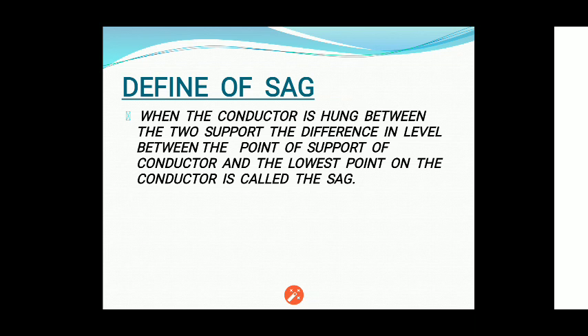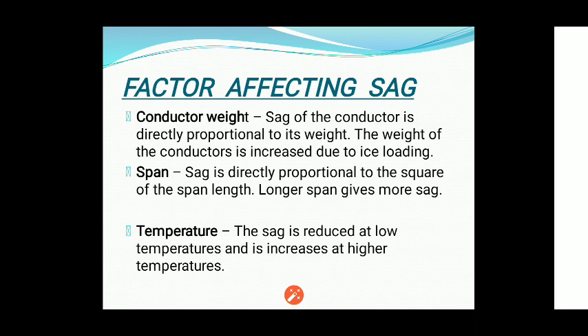Next we will discuss the factors that affect sag. The first factor is conductor weight — sag is directly proportional to the weight of the conductor, meaning if the weight of the conductor is more, then sag is more. The second factor is span — sag is directly proportional to the square of the span length. A longer span gives more sag.